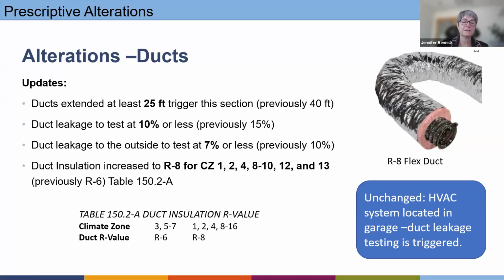If you have duct leakage that needs to be tested, it's got to be tested to 10% overall, and leakage to the outside of the house tested to 7%. This means you're going to have a HERS rater come out and do that duct leakage testing. And if your HVAC system is located in the garage, duct leakage testing is definitely triggered.